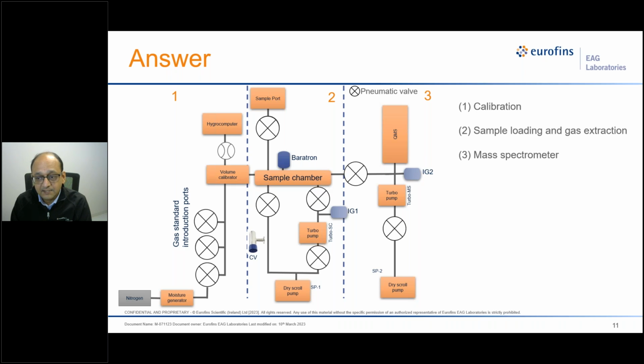And for the mil standard, we have to do a daily calibration where 5,000 ppm plus or minus 500 ppm moisture needs to be introduced in the sample chamber. And for almost every volume, we have to calibrate daily prior to running our tests. Now, what we have done is put a stricter criterion in here. Instead of 5,000 plus or minus 500 ppmv, we put 5,000 plus or minus 100 ppmv. So we have a narrower range of qualified gas that we will be supplying to the sample chamber. So that explains section 1.